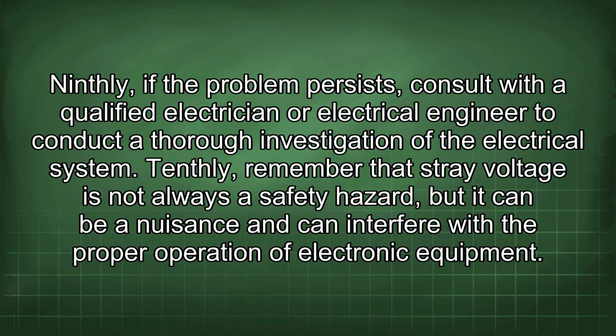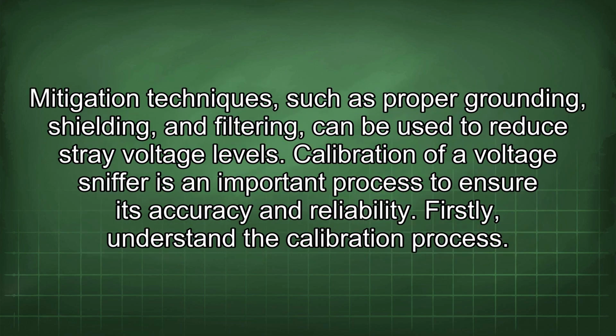electrical system. Tenthly, remember that stray voltage is not always a safety hazard, but it can be a nuisance and can interfere with the proper operation of electronic equipment. Mitigation techniques, such as proper grounding, shielding, and filtering, can be used to reduce stray voltage levels.